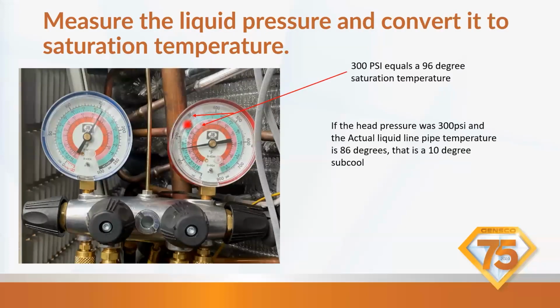And here again, say if we had 300 psi, our liquid line is right there about 96. So that's our saturation. So if the head pressure was 300, like we have here, the actual liquid line temperature was 86. So 86 would be right here. That would be a 10-degree subcool. So you're just going off of whatever our pressure is, whatever our saturation temperature with the corresponding pressure is. That's subcool.